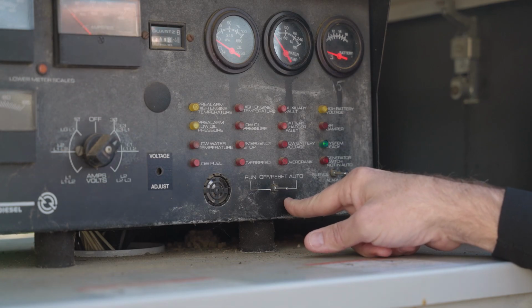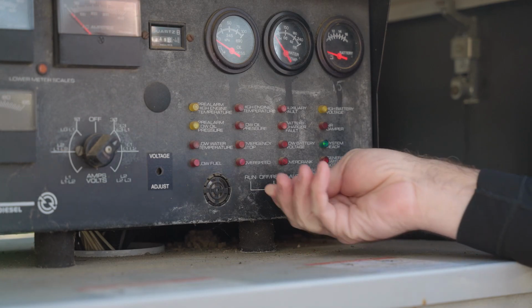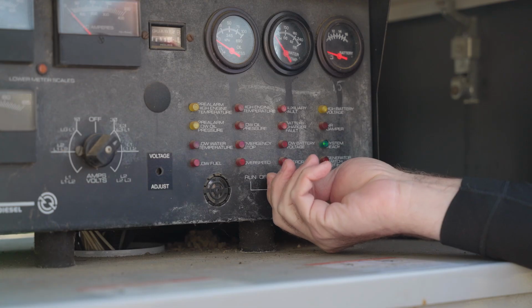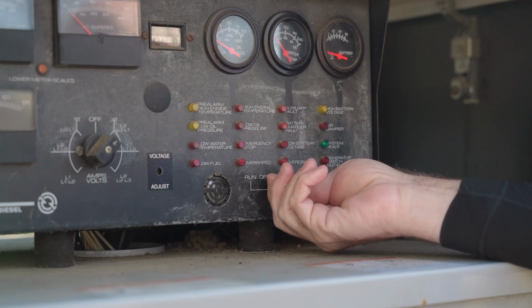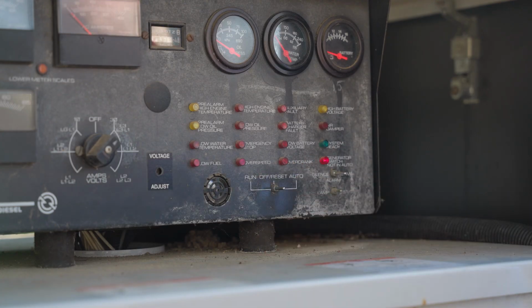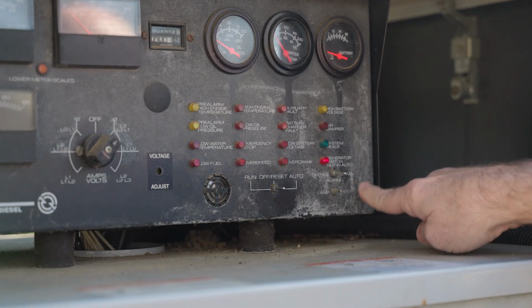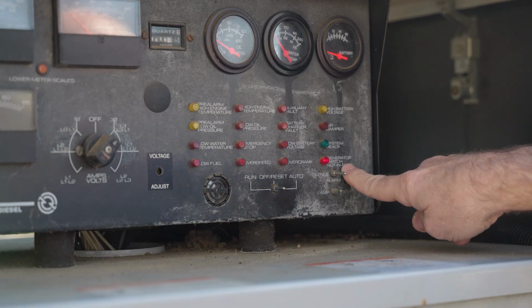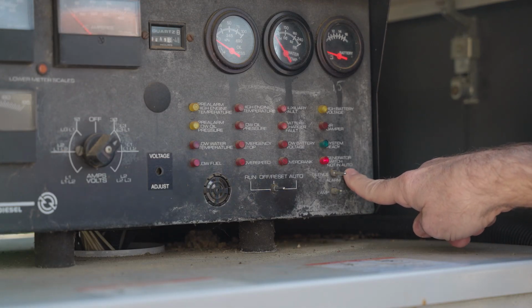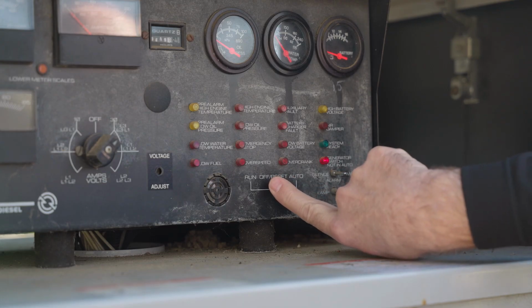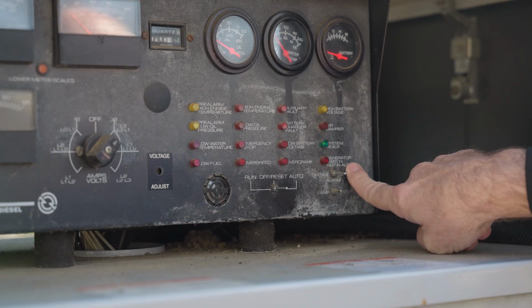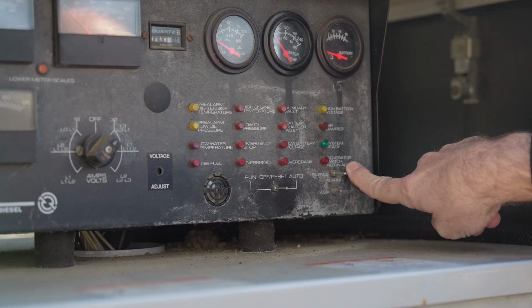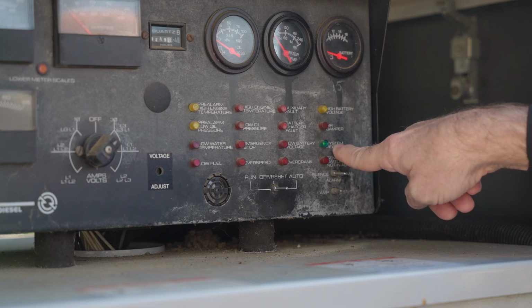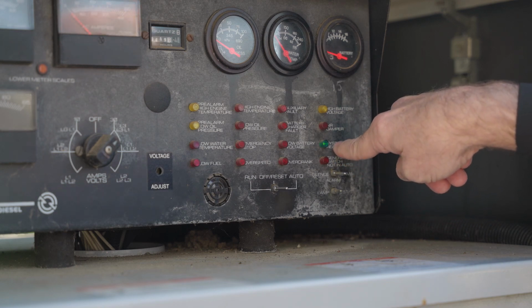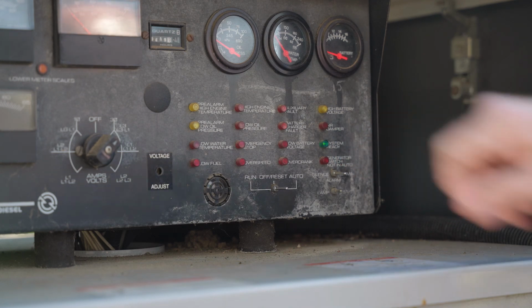The easiest way to tell if it's in the automatic position is it'll have an audible alarm if it's in the off position or reset position. So you can hear the noise from the buzzer. It also has a light telling you that the generator switch is not in automatic. If we flip it back to auto, our generator switch not in auto light goes out and our system ready light is back on. This means your generator is ready to run in case of an outage.